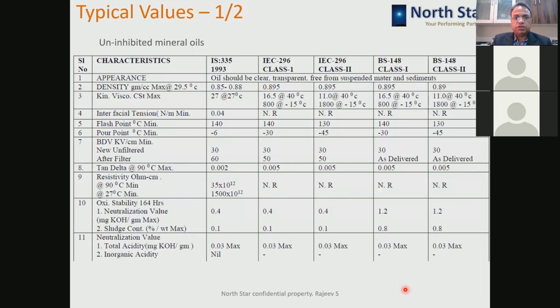So that point is to be taken into consideration when we are referring to these standards with respect to natural and synthetic esters. These are the typical values as per different standards for the new or virgin insulating mineral oils. We'll see for IS 335, appearance like this, density is 0.85 to 0.88. So these are the properties which are applicable for new transformer oil. Flash point, you can see it is 140, pour point is -6. BDV of unfiltered oil, when you are receiving it in a tanker in your factory, is 30 kV, and when you filter it, it should be minimum 60 kV.